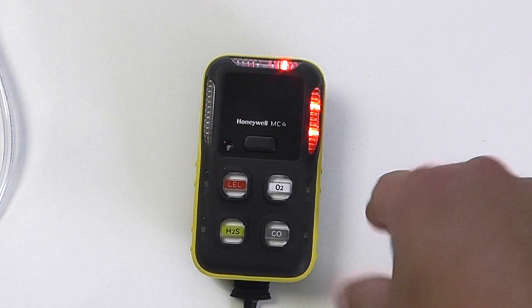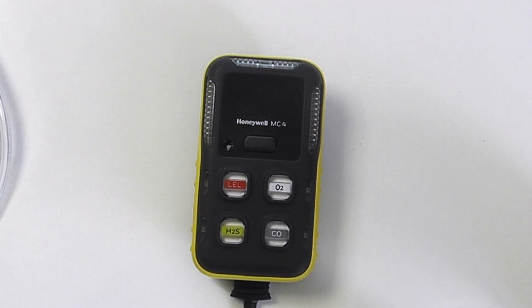We can now see an alarm level one, and this is only on the LEL sensor. Clear that on the O2, and it's letting us know our H2S sensor needs a calibration.